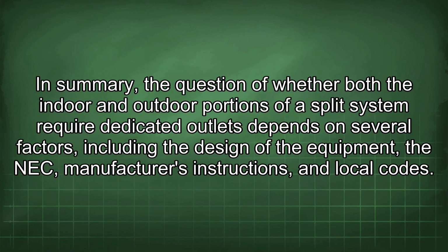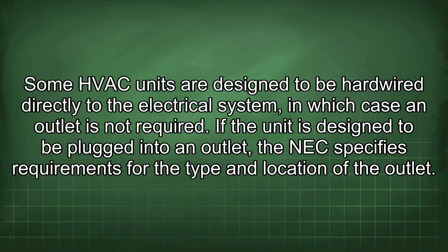In summary, the question of whether both the indoor and outdoor portions of a split system require dedicated outlets depends on several factors, including the design of the equipment, the NEC, manufacturer's instructions, and local codes. Some HVAC units are designed to be hardwired directly to the electrical system, in which case an outlet is not required.